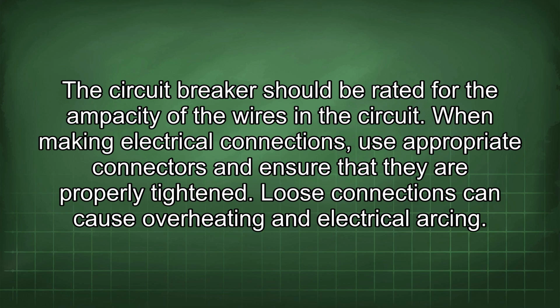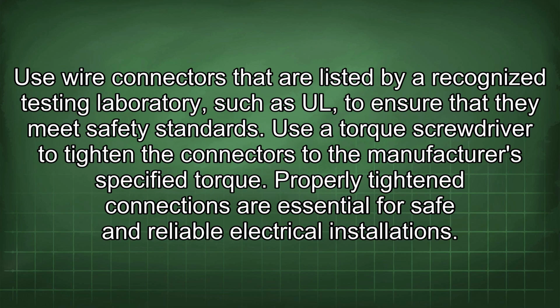When making electrical connections, use appropriate connectors and ensure that they are properly tightened. Loose connections can cause overheating and electrical arcing. Use wire connectors that are listed by a recognized testing laboratory such as UL to ensure that they meet safety standards. Use a torque screwdriver to tighten the connectors to the manufacturer's specified torque. Properly tightened connections are essential for safe and reliable electrical installations.